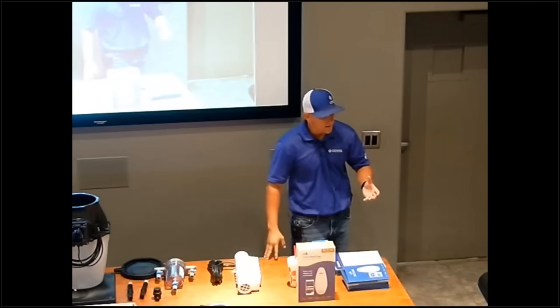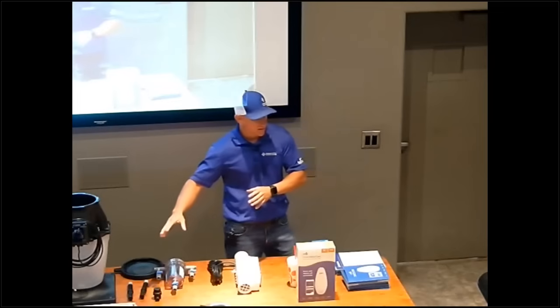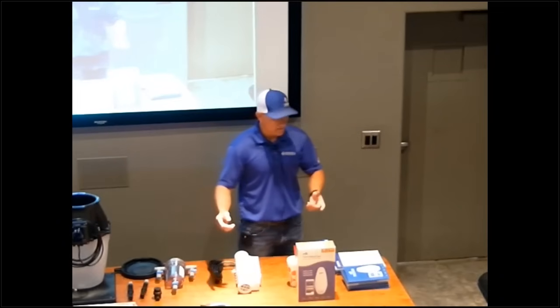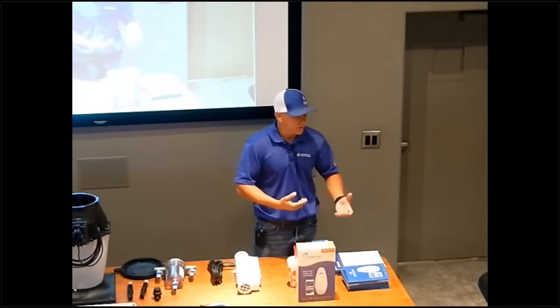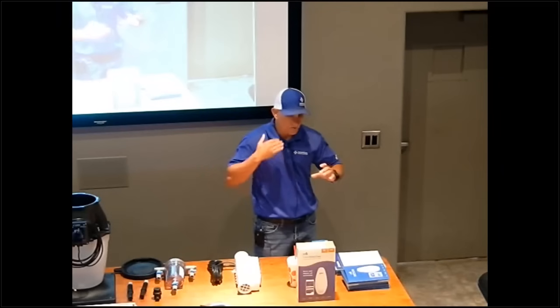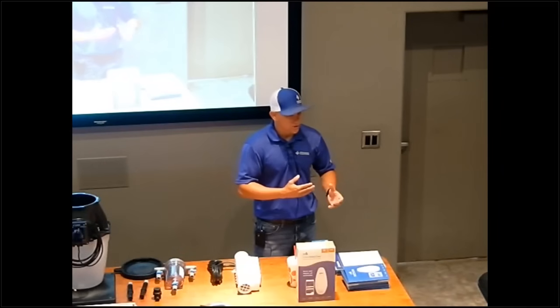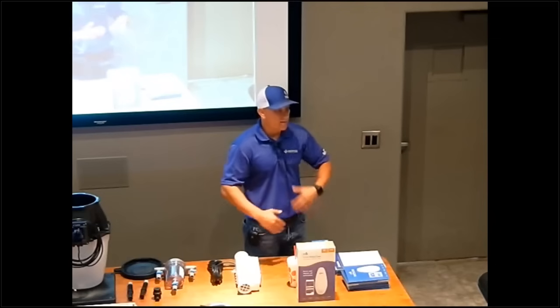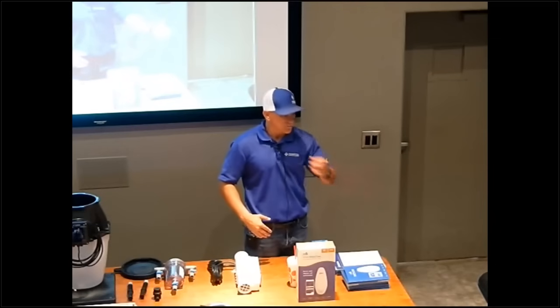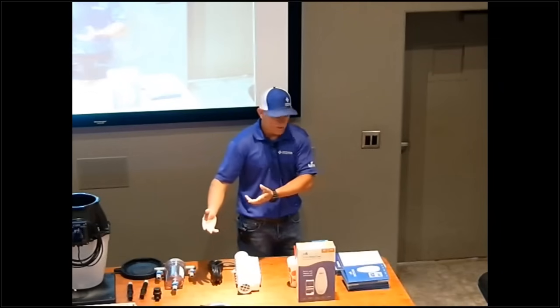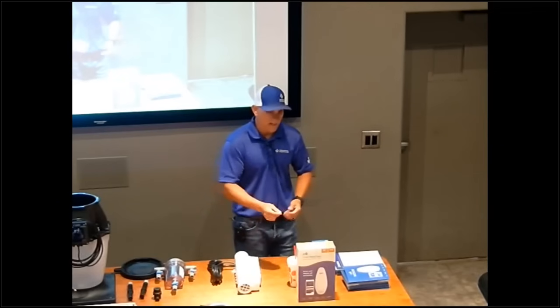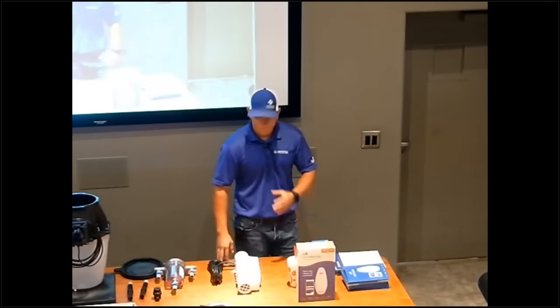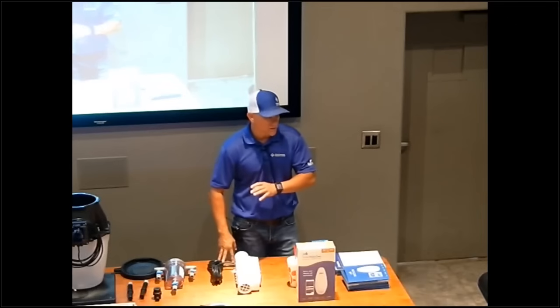The problem with manual adjustment is the benefit of this system - it's doing the testing and adjusting for you. Where if you just get accustomed to putting something in routinely, next thing you know your pH is really low, and that's acidic, aggressive, corrosive water. But without a system like this, you have no clue - you're just winging it.